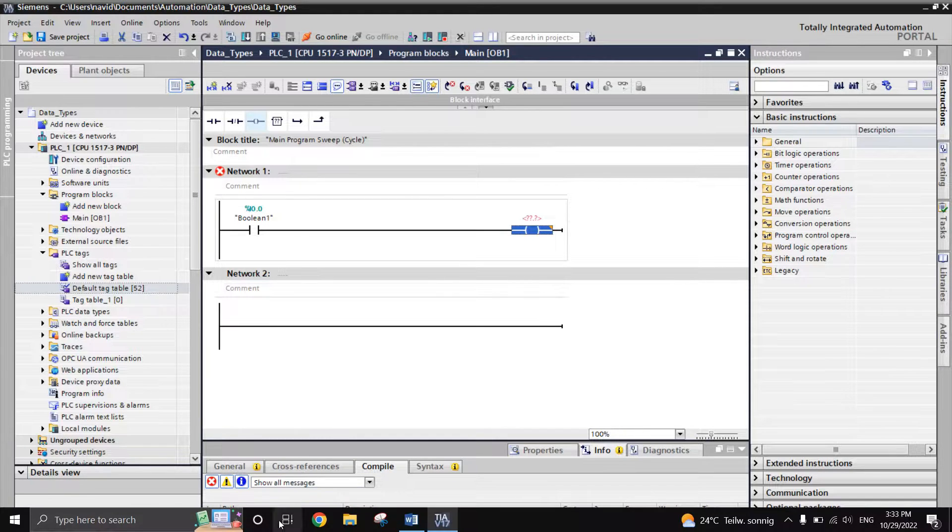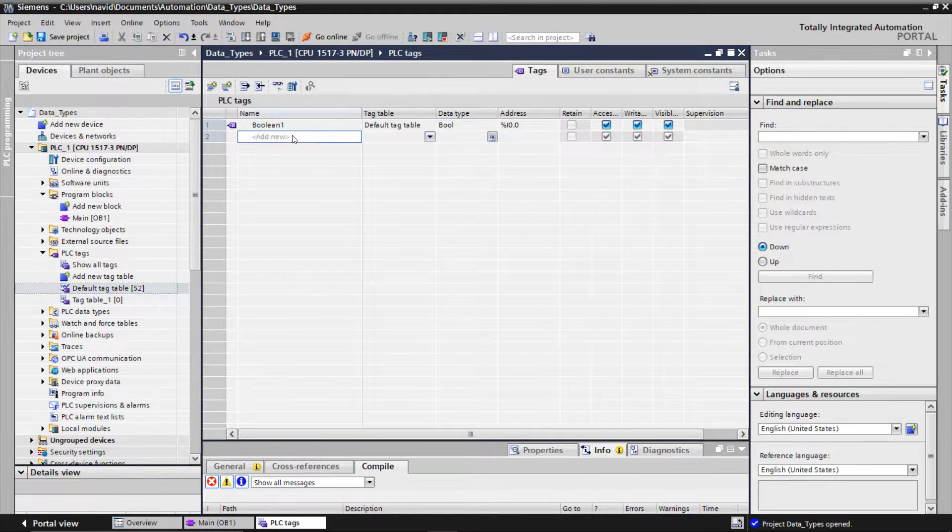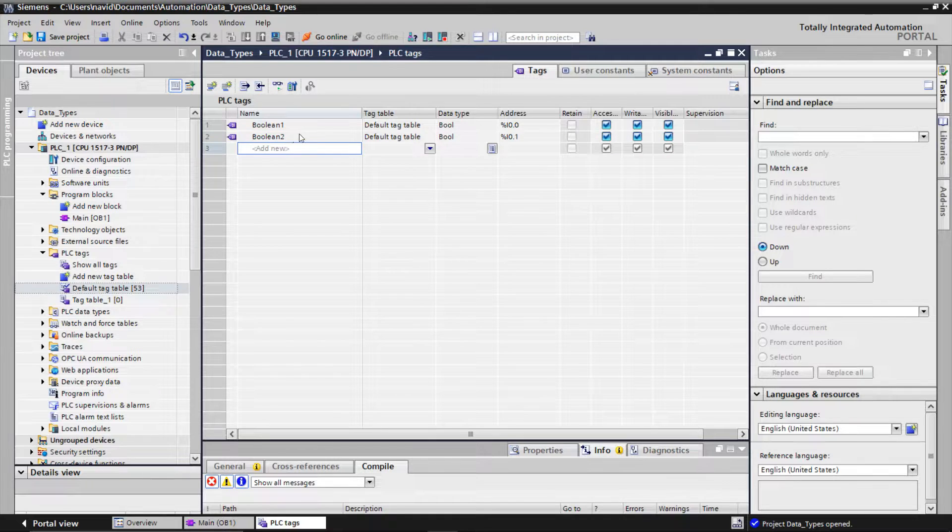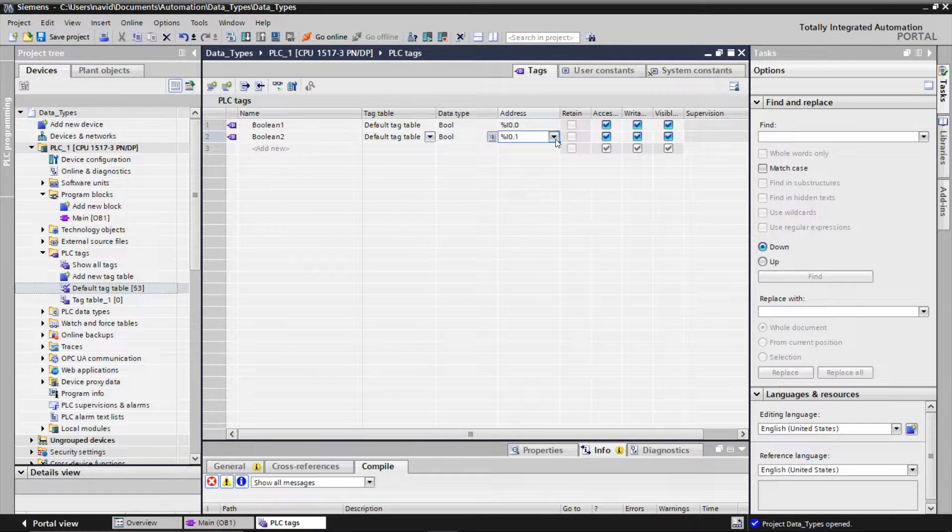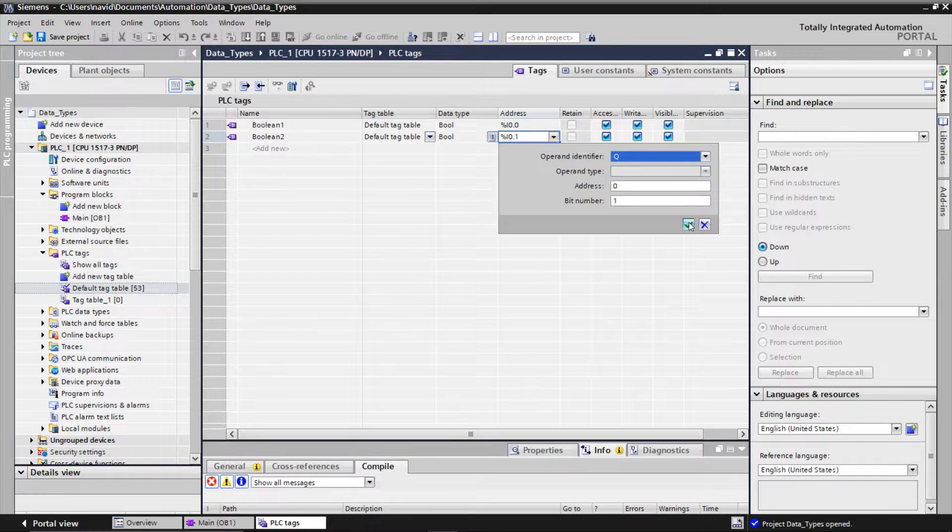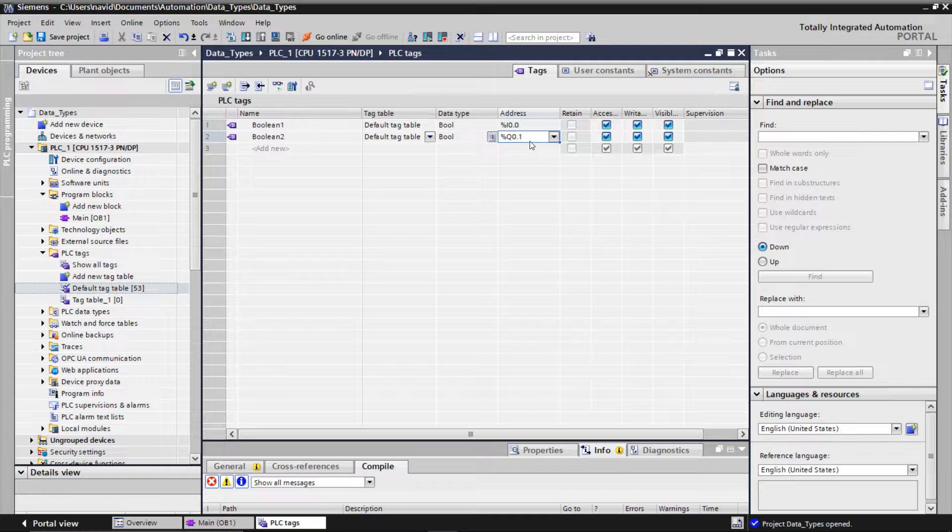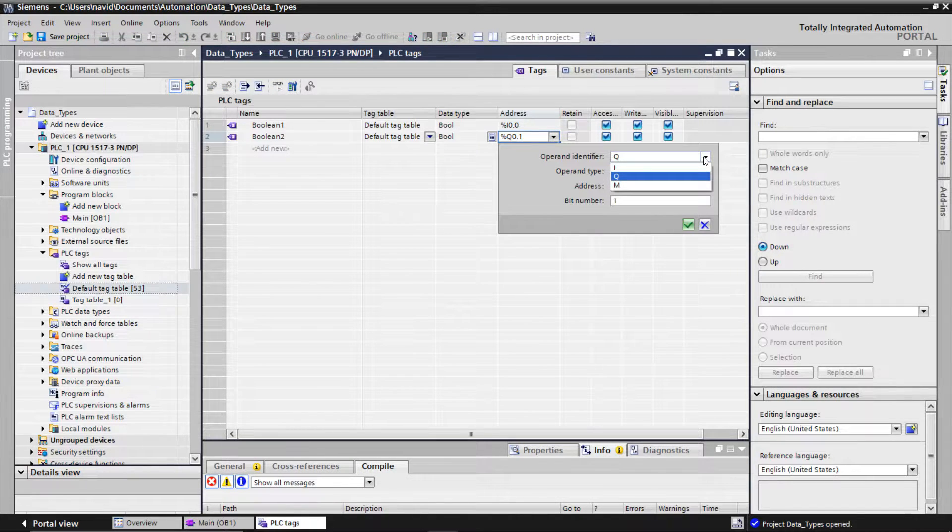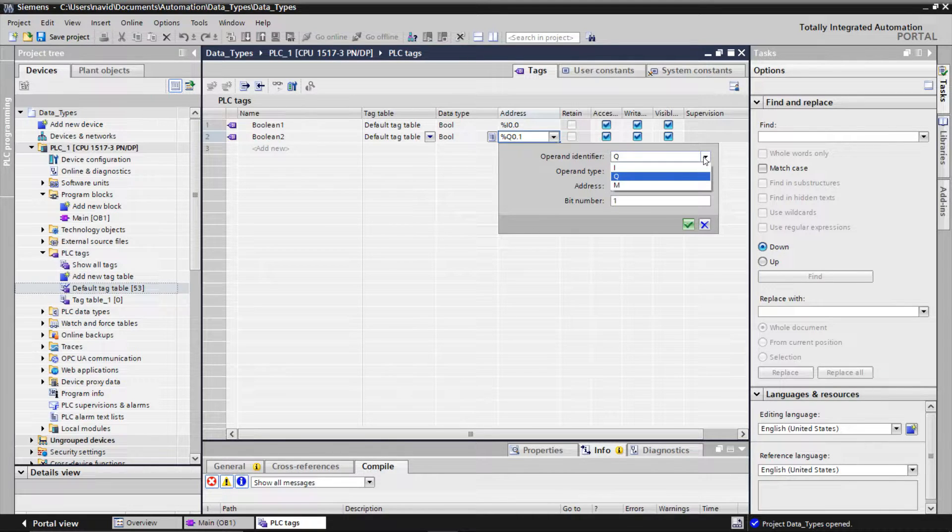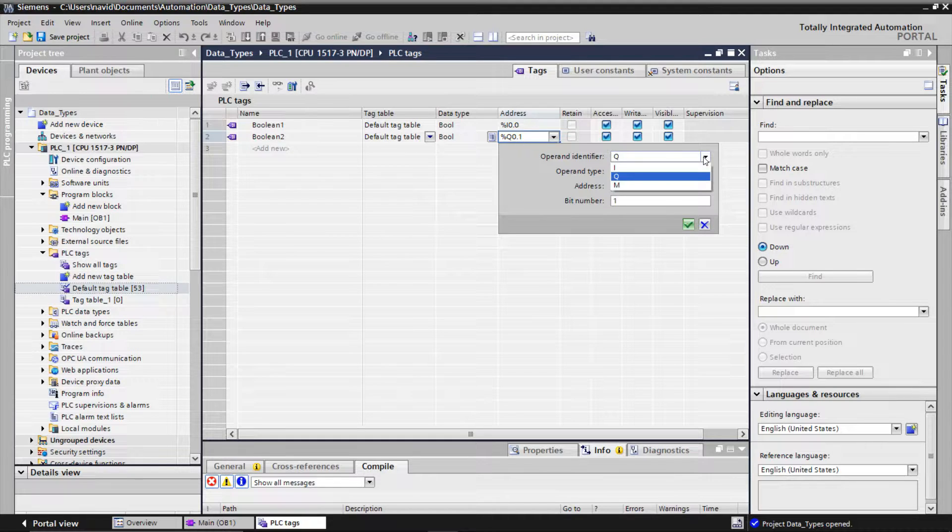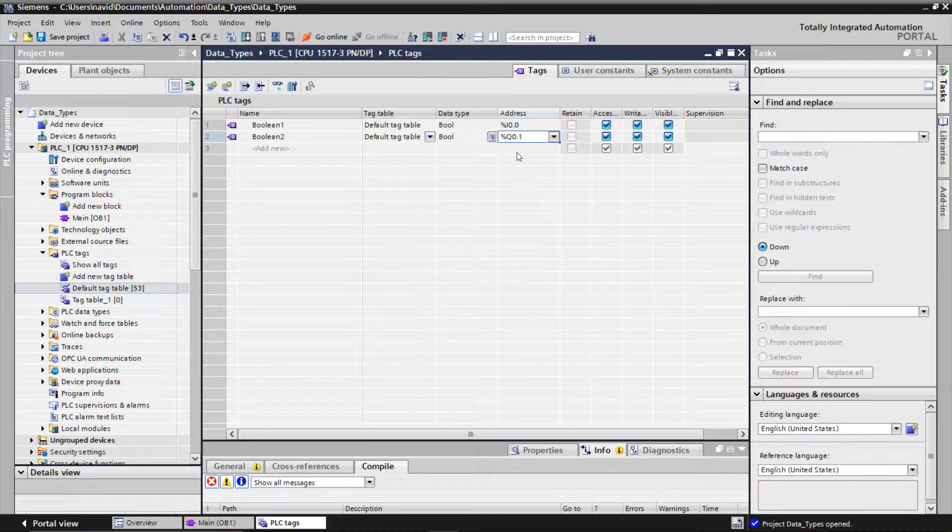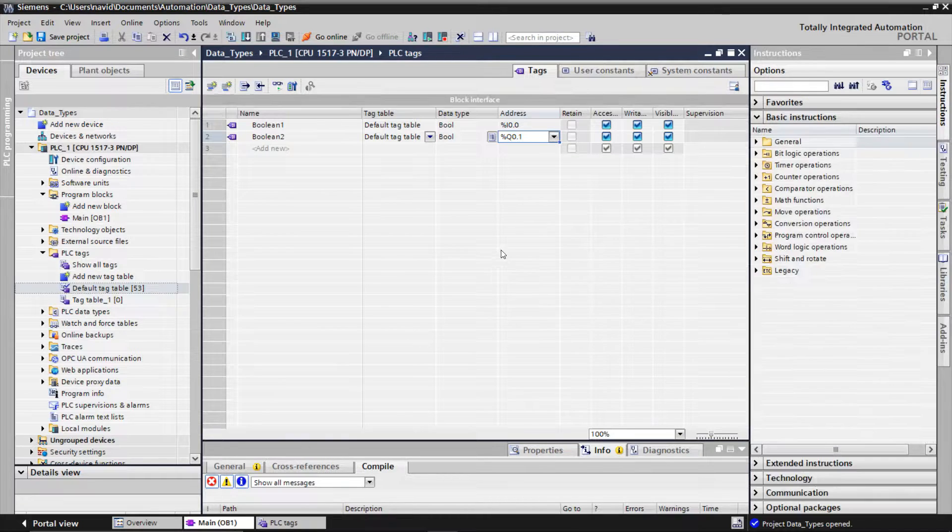Let me create another boolean. So we use I0.0, Q0.0 or M0.0. If you remember, M indicates memory. Other variables can sit in the input, output or memory. The first number refers to the byte number and the second number determines the bit number, which can be 0 to 7.